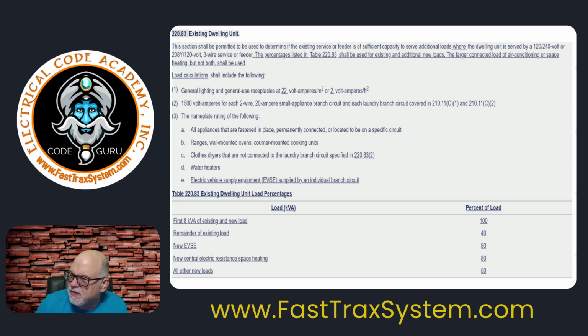It says all appliances that are fastened in place, permanently connected, or located to be on a specific circuit. That didn't change, right? The next one, B, is ranges, wall-mounted ovens, counter-mounted units, so just gather that info. C, clothes dryers that are not connected to the laundry circuit. Makes sense. D is water heaters. Same. So far, everything looks pretty much the same, except we dropped the 3 VA down to 2 VA, right?